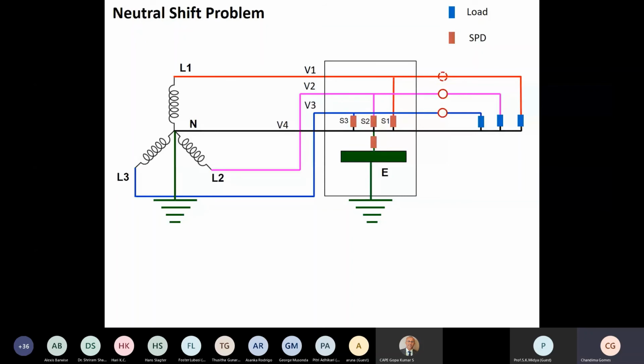And then maybe this is my last slide, or one before last, neutral shift problem. We have another problem when it comes to the SPDs. Now imagine we have a system like that where the line 1 is now switched on. So that means the load which is connected to line 1 is being operated. While L1 is feeding the load, there will be a neutral break. Say somebody cut the neutral or a tree falls onto the neutral, then we say that the neutral is broken. Now what happens? There will be no current flow in the line L1. Therefore, the whole voltage in the line L1 will be the same. So in other words, V4, earlier the neutral voltage, now goes to V1.